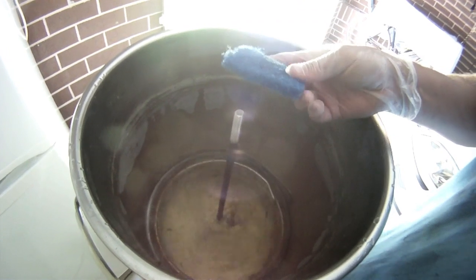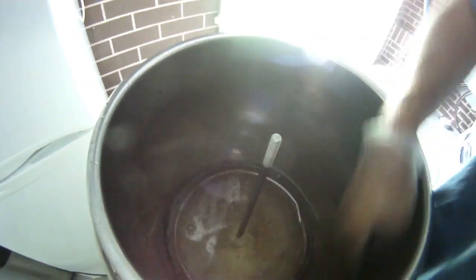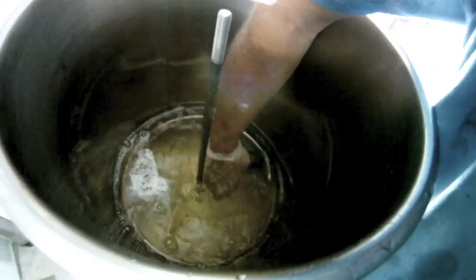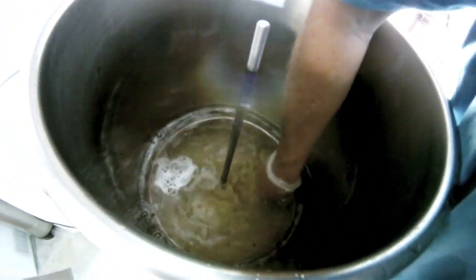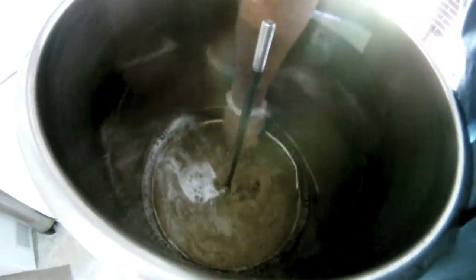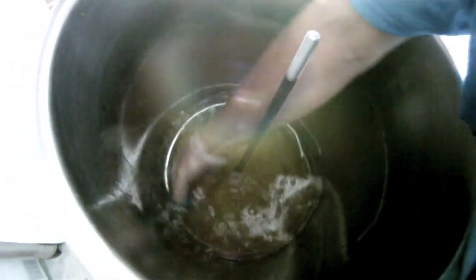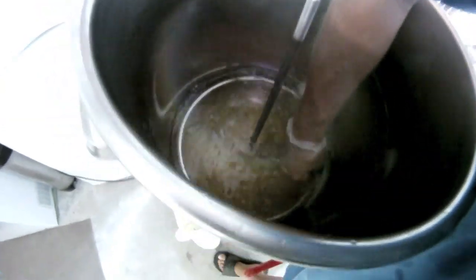A little bit of a scrubby pad, nothing too drastic - caustic soda really rips this material off. And then what I do is I wrap it around the element, because even though it's on, there's so much surface area it doesn't actually get that hot to touch. So I just wrap that around, run it around the element, and then go down to the next level.